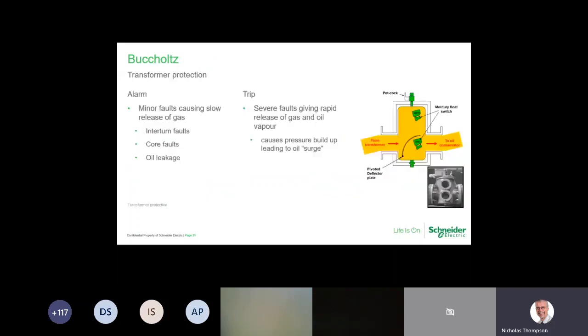And the Buchholz sits in a pipe between the conservator and the transformer tank. It will have an alarm contact, it will have a trip contact, and for low-level faults where you may just want an alarm, that's when it will trigger. And you can also collect the gas for analysis as well. For a high level fault where you're going to get hot oil and gases flowing quite rapidly from the transformer tank up into the conservator, that's where the trip contact will actually work.